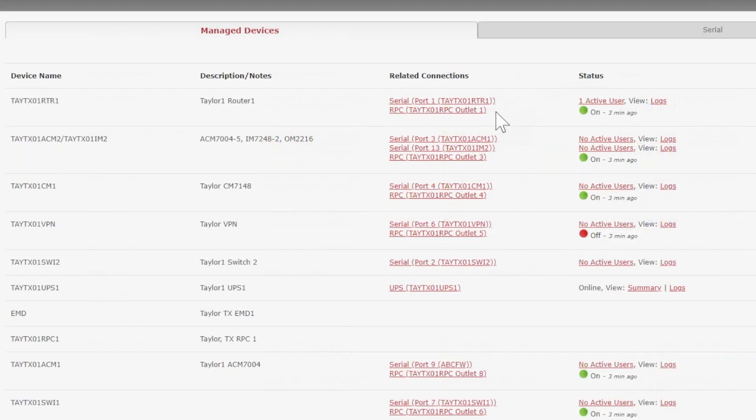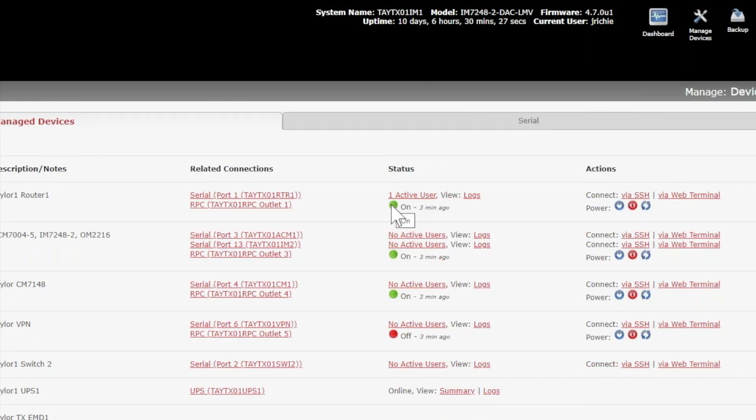When you logically map an outlet from a remote power controller strip to a serial port on the OpenGear, it gives you the ability to view the state of that power on the outlet that you've mapped. But more than that, it gives you the ability to control that power.